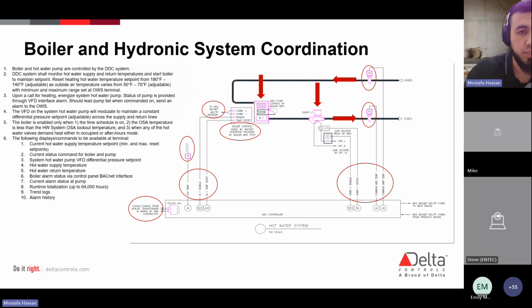And then the following points will be displayed on your operating workstation, or will be programmed through your controller, right? Now, a lot of these points are hardwired, real points, and some of these are virtual. Virtual could be like your runtime, right? How long has this pump been working? How long has the boiler been working? But in this case, there's no real lead lag, so there's no alternating between this pump and another pump. All these points will be visible at the operating workstation and monitored through these devices laid out here or through virtual points that are created by the controls contractor or technician.